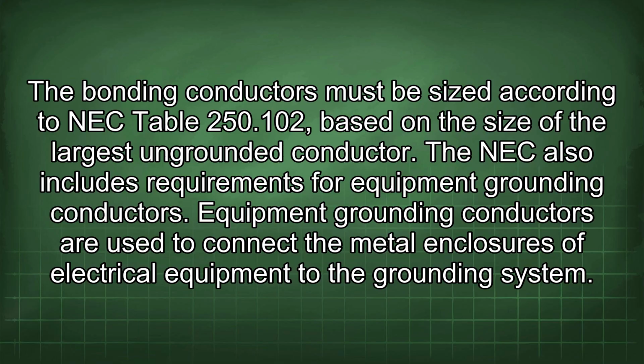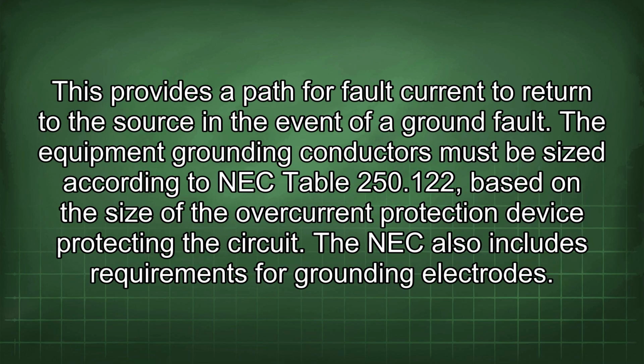The NEC also includes requirements for equipment grounding conductors. Equipment grounding conductors are used to connect the metal enclosures of electrical equipment to the grounding system. This provides a path for fault current to return to the source in the event of a ground fault. The equipment grounding conductors must be sized according to NEC Table 250.122, based on the size of the overcurrent protection device protecting the circuit.